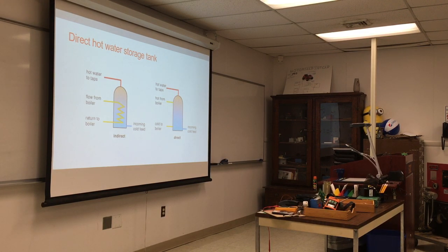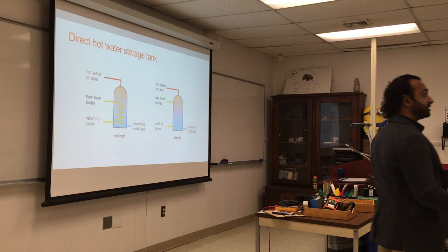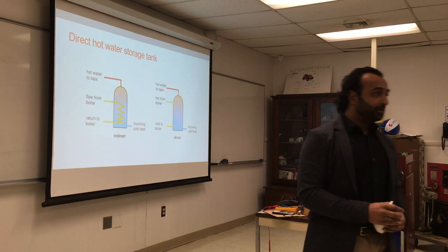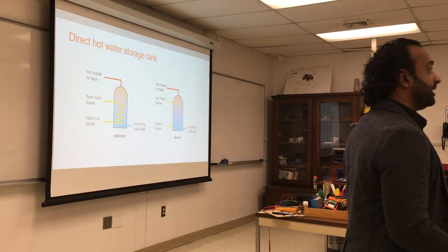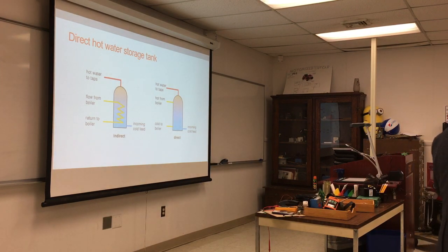Others could use hot water as well, at the same time. Could be, what else? If you're trying to get it higher up in the building, if there's more distance in the winter, if it's 0 outside and so cold, probably if you leave it at 140, it's not going to go hot all the way there. So in the winter, you'll probably adjust that a little bit, or in the summertime, you can turn it down again. So it could be the distance, could be the insulation. On a very, very cold day, if you store the water at 140, by the time it gets to the second or third floor, it just doesn't get hot enough.